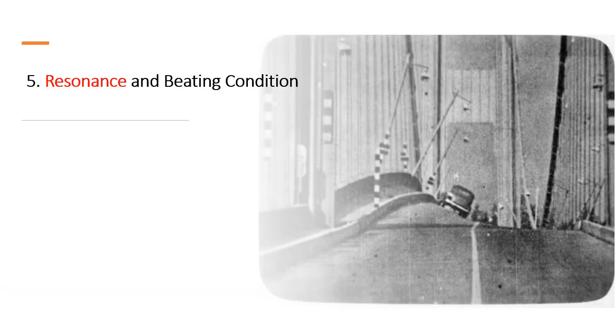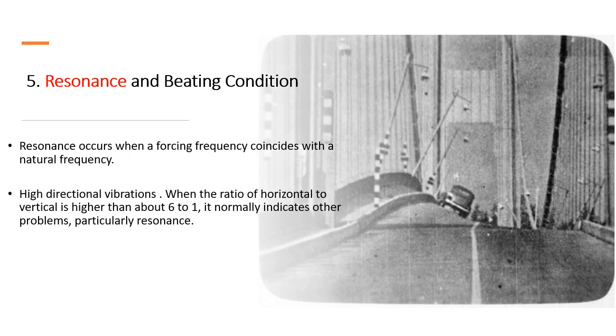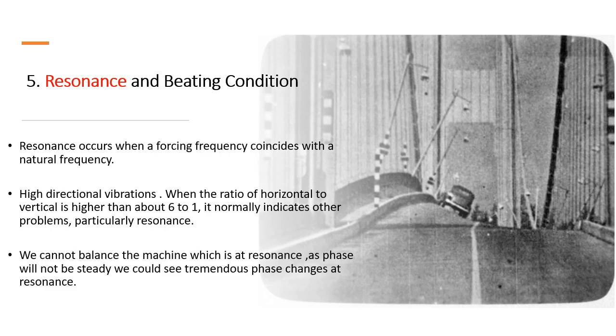The fifth reason is the resonance and beating condition. Resonance occurs when the forcing frequency coincides with the natural frequency. A key indicator is highly directional vibration — a ratio of 6:1 or higher from one direction to another (e.g., horizontal to vertical) normally indicates problems other than unbalance, particularly resonance. You cannot balance a machine at resonance, as the phase will not be steady, and you will see a 90-degree phase shift and a 180-degree phase shift as the rotor passes through resonance.